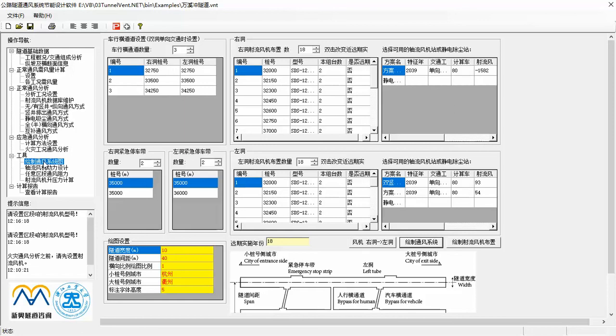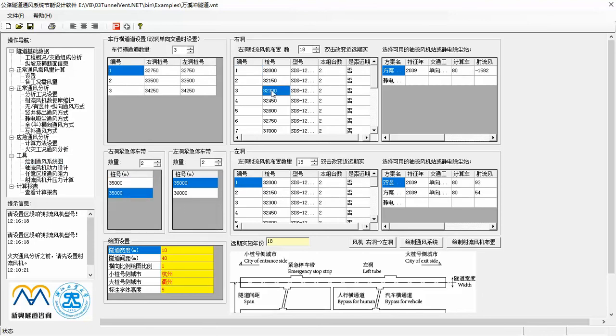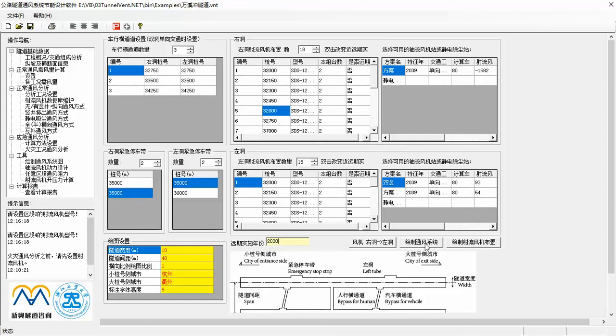Firstly, in this interface, you need to input the mileage of bypasses or connection channels, emergency stopping bays, and jet fans mounted in both tubes. Select one longitudinal ventilation scheme, then click this button, the ventilation system diagram will output in DWG format. Here is the example.